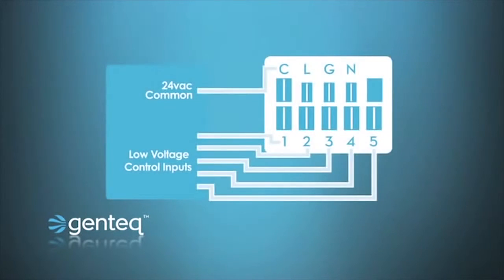Next is the communication inputs. On the X13, there's 5 communication inputs. They're often called speeds, but they're actually torque settings that can be programmed by the manufacturer. So the OEM manual will be needed for each appliance that uses X13 to know which taps are being used for heat, cool, fan, exactly what they're programmed for.